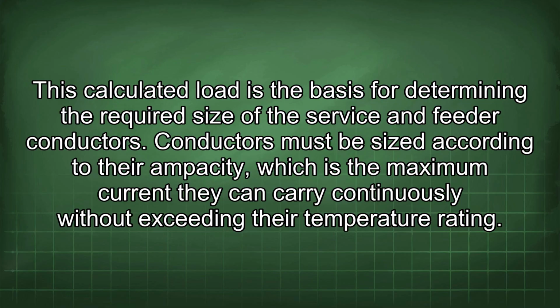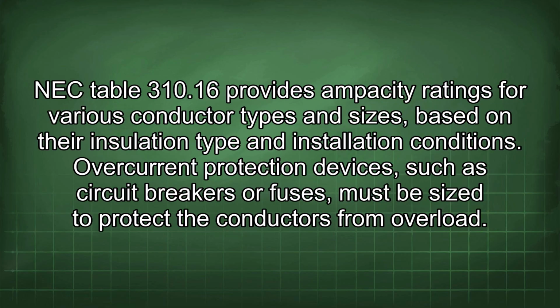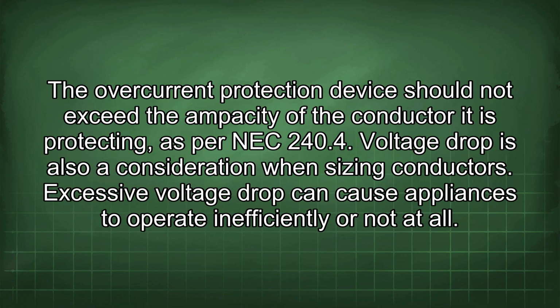Conductors must be sized according to their ampacity, which is the maximum current they can carry continuously without exceeding their temperature rating. NEC Table 310.16 provides ampacity ratings for various conductor types and sizes, based on their insulation type and installation conditions. Overcurrent protection devices, such as circuit breakers or fuses, must be sized to protect the conductors from overload. The overcurrent protection device should not exceed the ampacity of the conductor it is protecting, as per NEC 240.4.